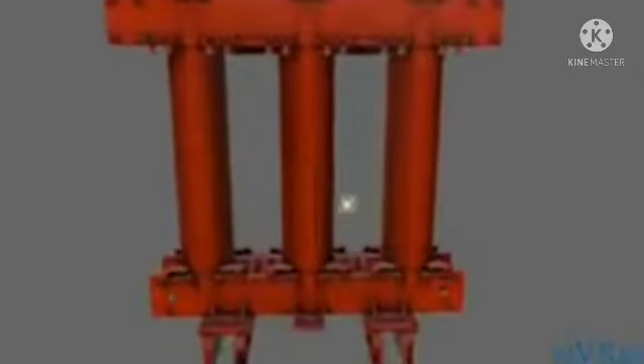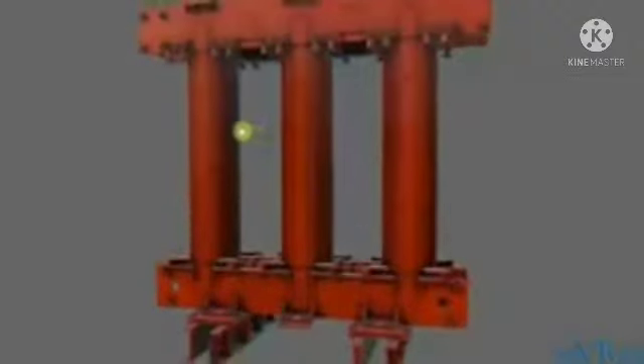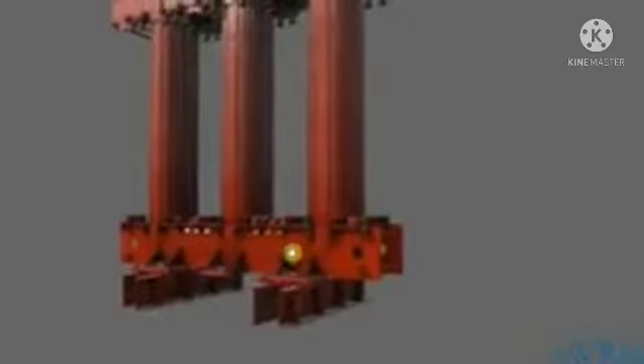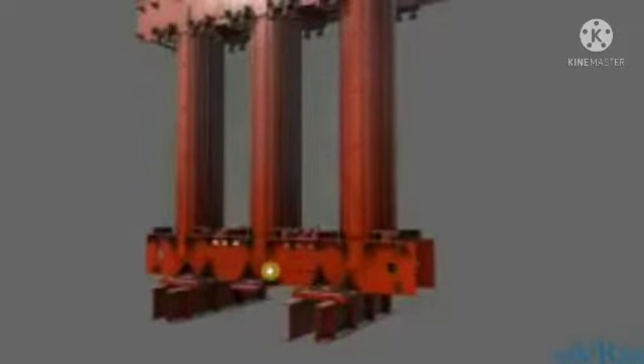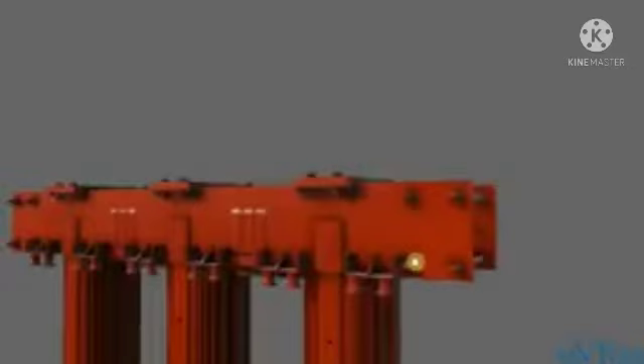So we've got our limbs, 1, 2, 3. We've got the yokes at the top and the bottom of the core, and the core itself consists of very thin steel laminations that have been clamped together and have been isolated from each other, usually by using some form of lacquer or coating. And then once it's all together, we're going to clamp it together or perhaps glue it together, and that is our transformer core. The rest of the assembly that we're looking at now is simply to hold the core in position. So we can see in the section at the bottom here, that is to secure the core in the base of the transformer to make sure it doesn't move around. And we can see at the top as well, we also have this installation to secure it to the top of the tank. And again, this stops any movement of the core within the transformer casing.